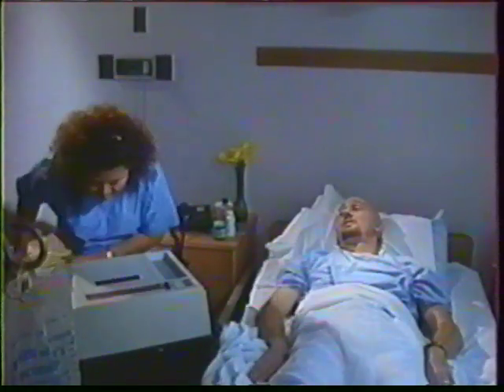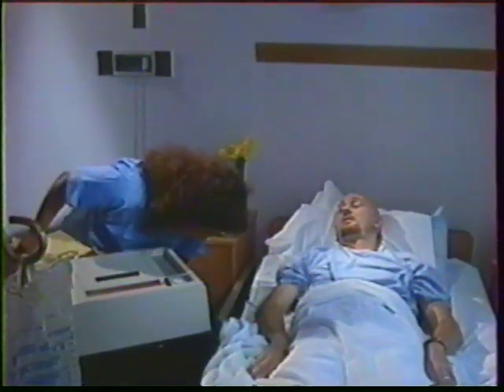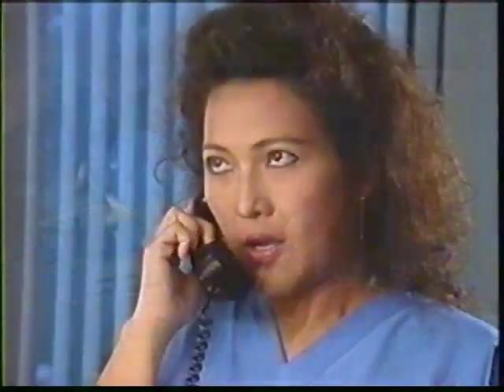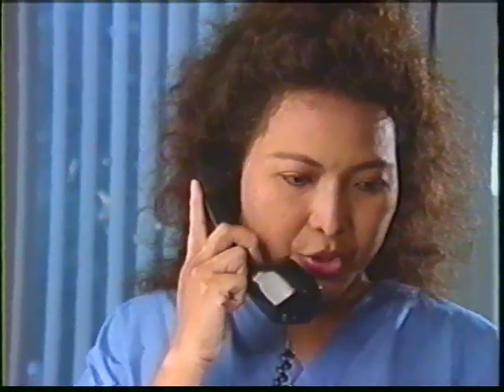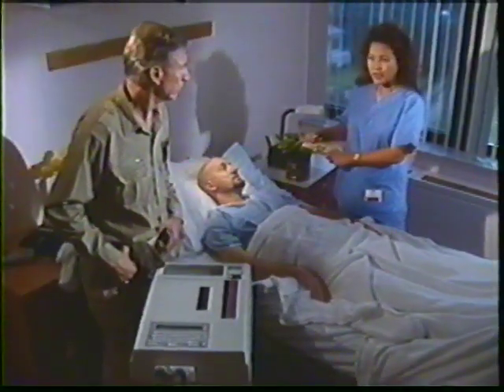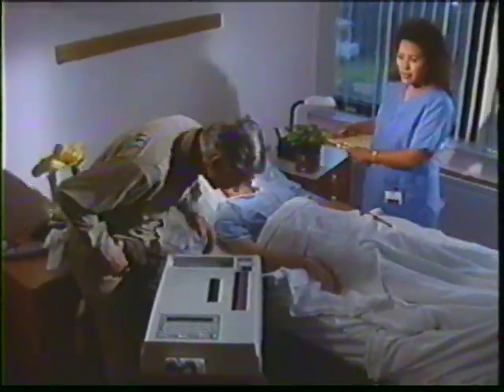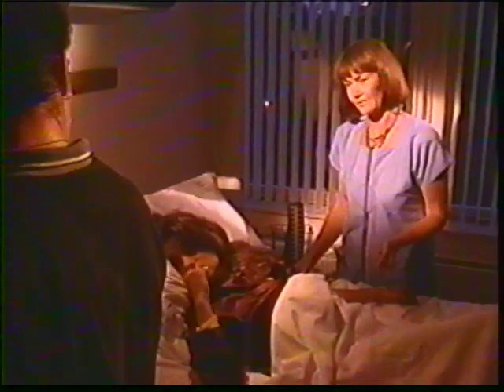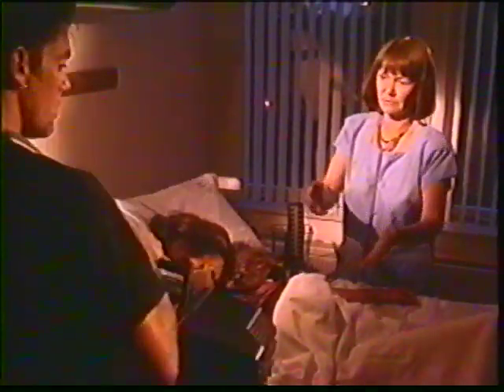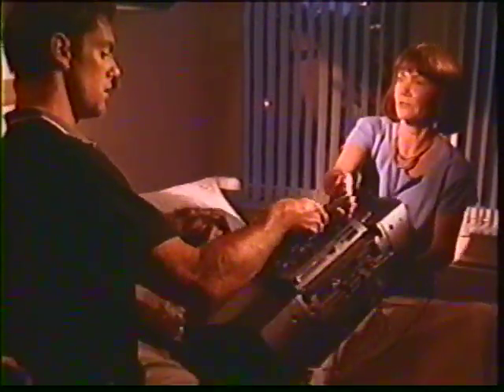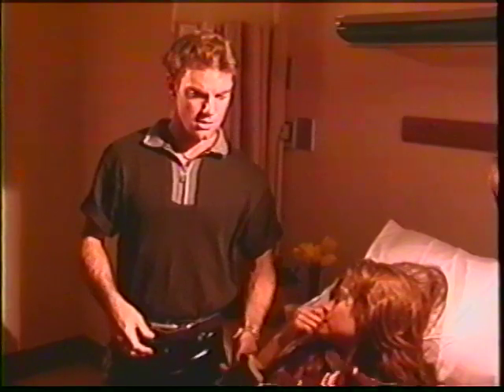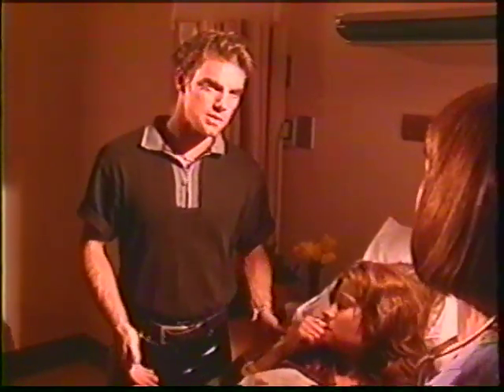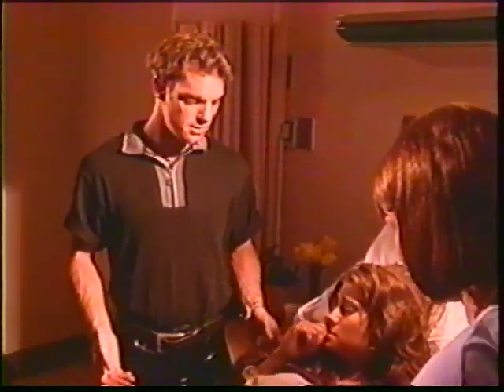Immediately investigate any strange or unusual smell coming from a piece of equipment, since an odor is often the first warning of fire. Stop using that piece of equipment until checked out. Many fires have occurred due to faulty electrical equipment brought in by patients or family. If your facility allows equipment to be brought in, have it checked for safety by the appropriate person. Safety and prevention is your goal.